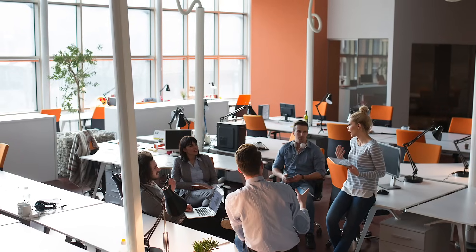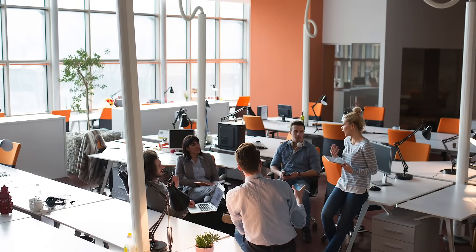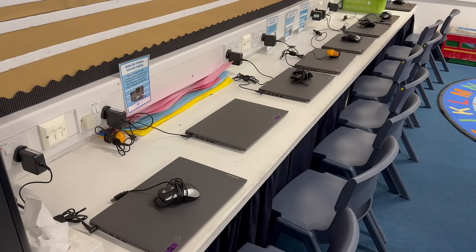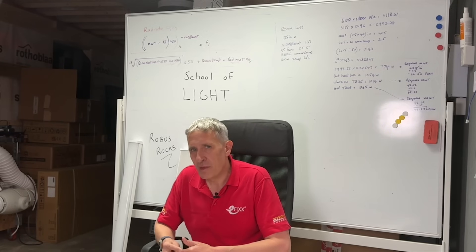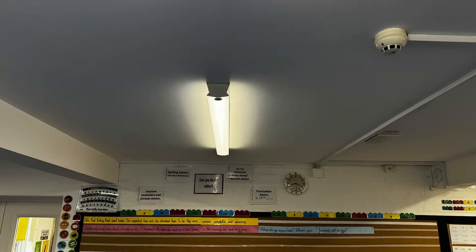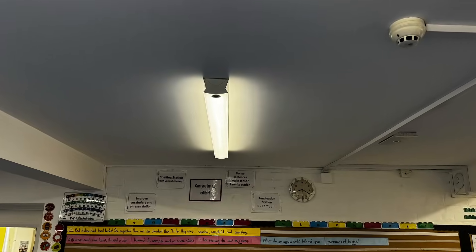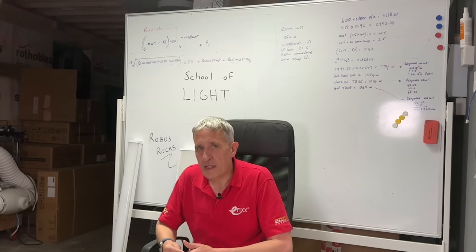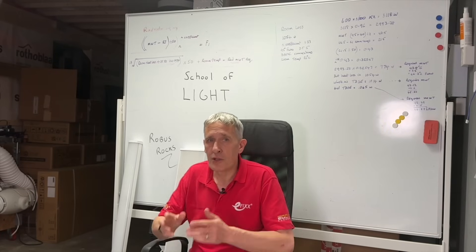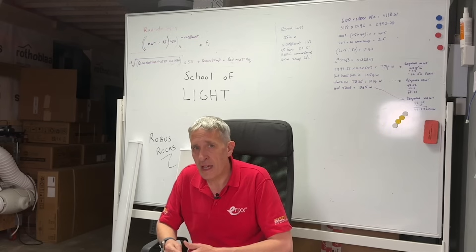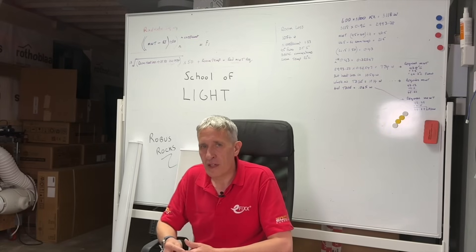When in a classroom or office setting, we need to reduce the amount of glare, as we tend to focus on reading from books or display screens. Excessive glare can cause eye strain, leading to headaches, so choose a fixture with low glare. While the fixture may be labelled with a glare rating of UGR19, as we learned in physics, the actual glare level is influenced by the specific lighting installation. Therefore, the fixture alone does not guarantee low glare. Instead, it contributes to achieving reduced glare within a comprehensive lighting design.